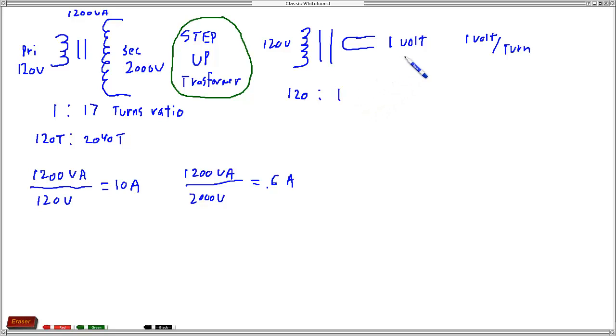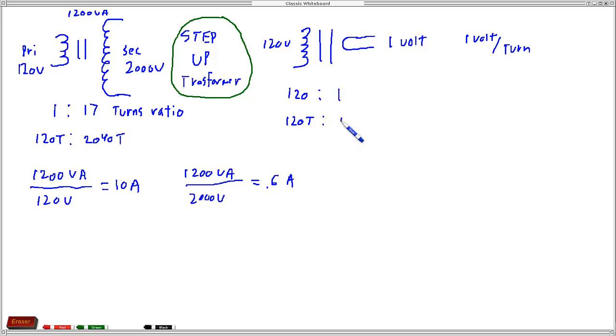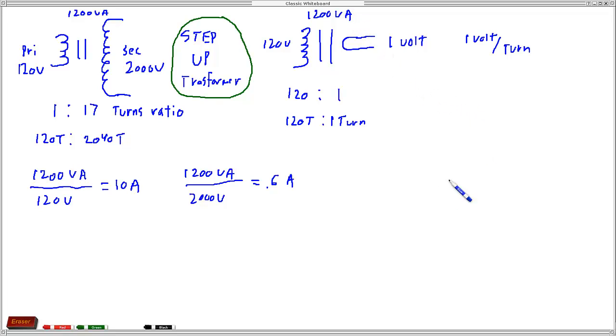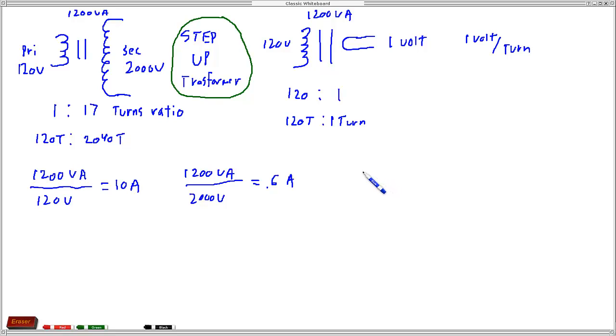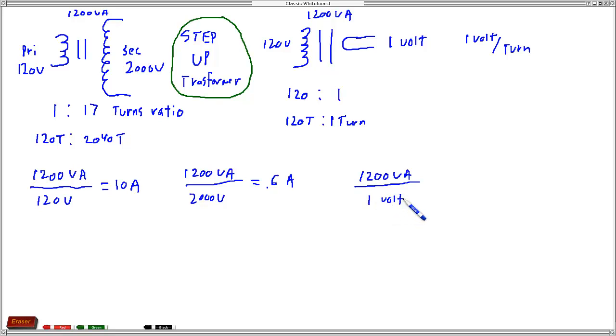So let's do the math here. Here we know we've got 120 volts and one volt. We have how many turns? 120 turns equals one turn over here. And we still have our 1200 VA rating here. That's the property of the transformer. So on the primary we still have 10 amp capability because that's just going to be 1200 VA divided by 120. That didn't change. But on our secondary, our VA rating is 1200 VA divided by one volt, which is going to be 1200 amp capability.